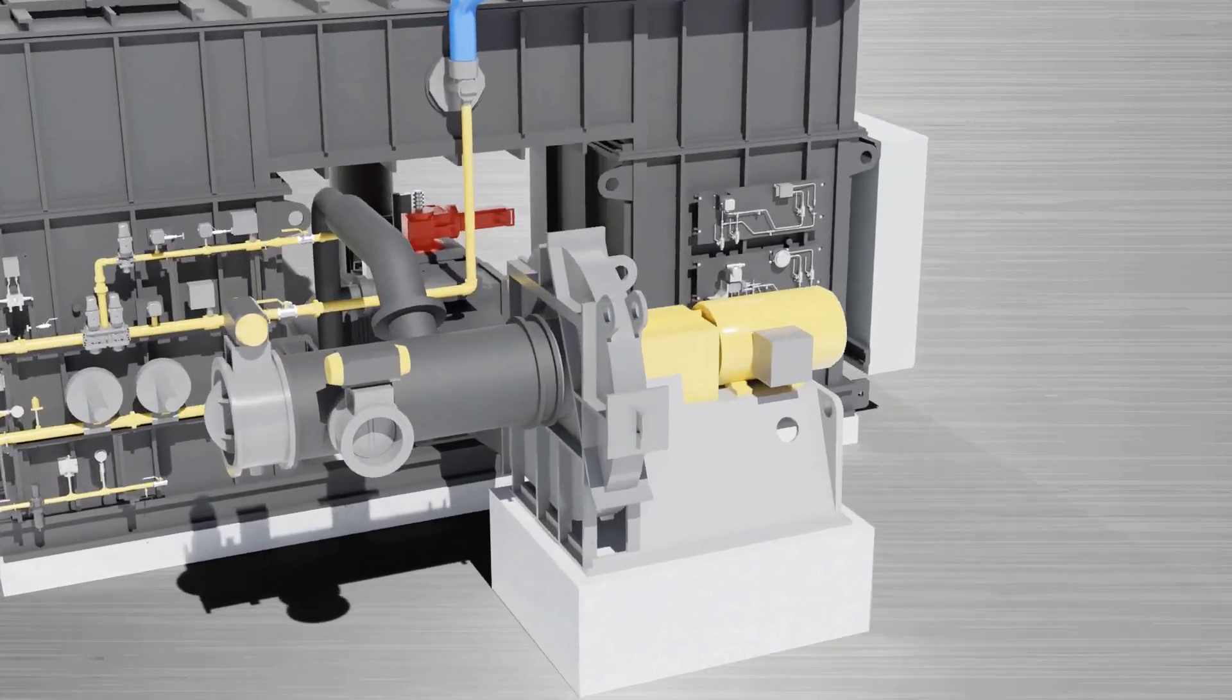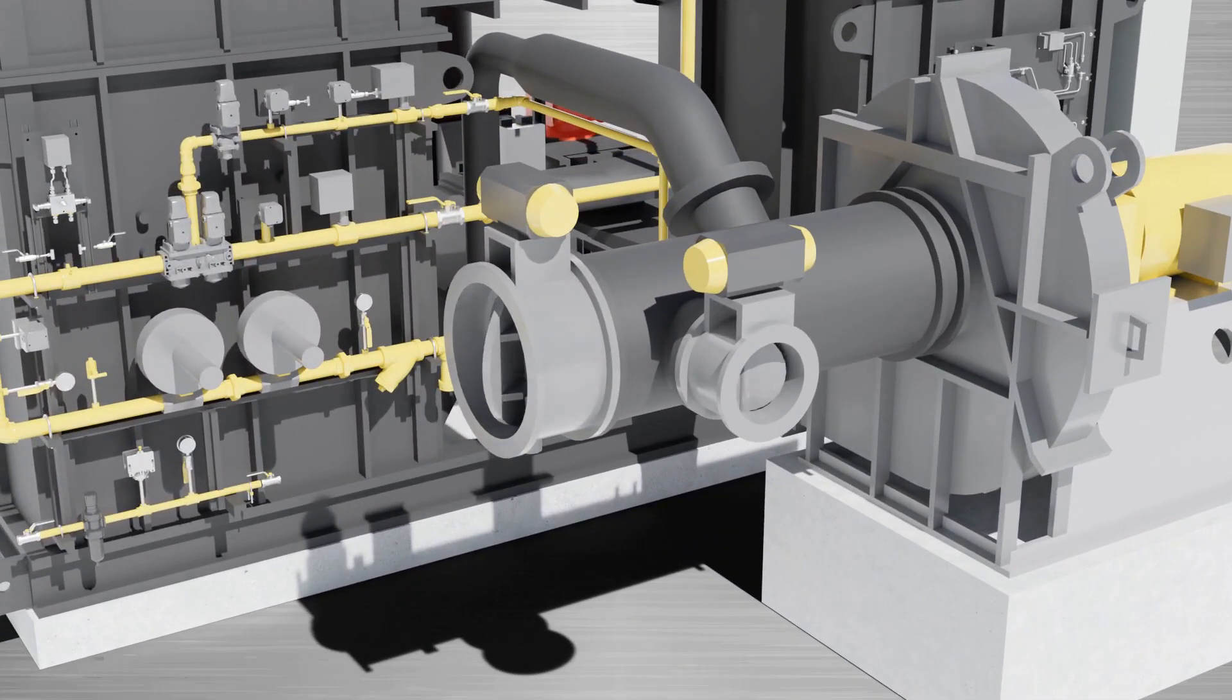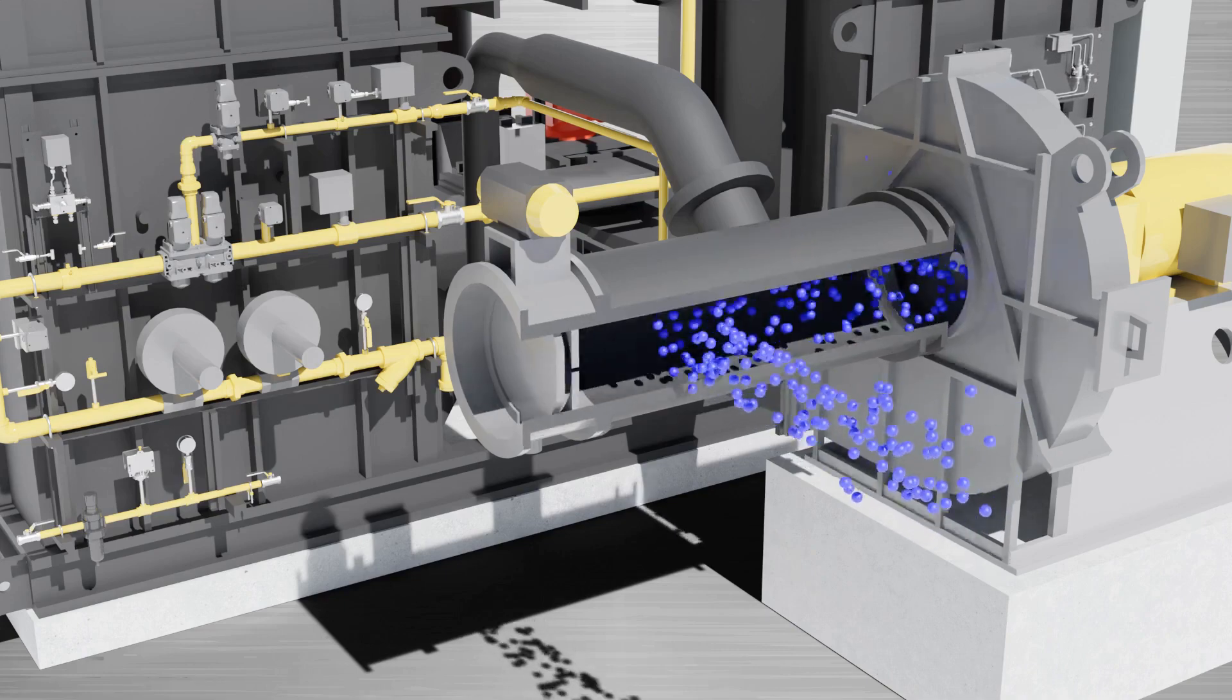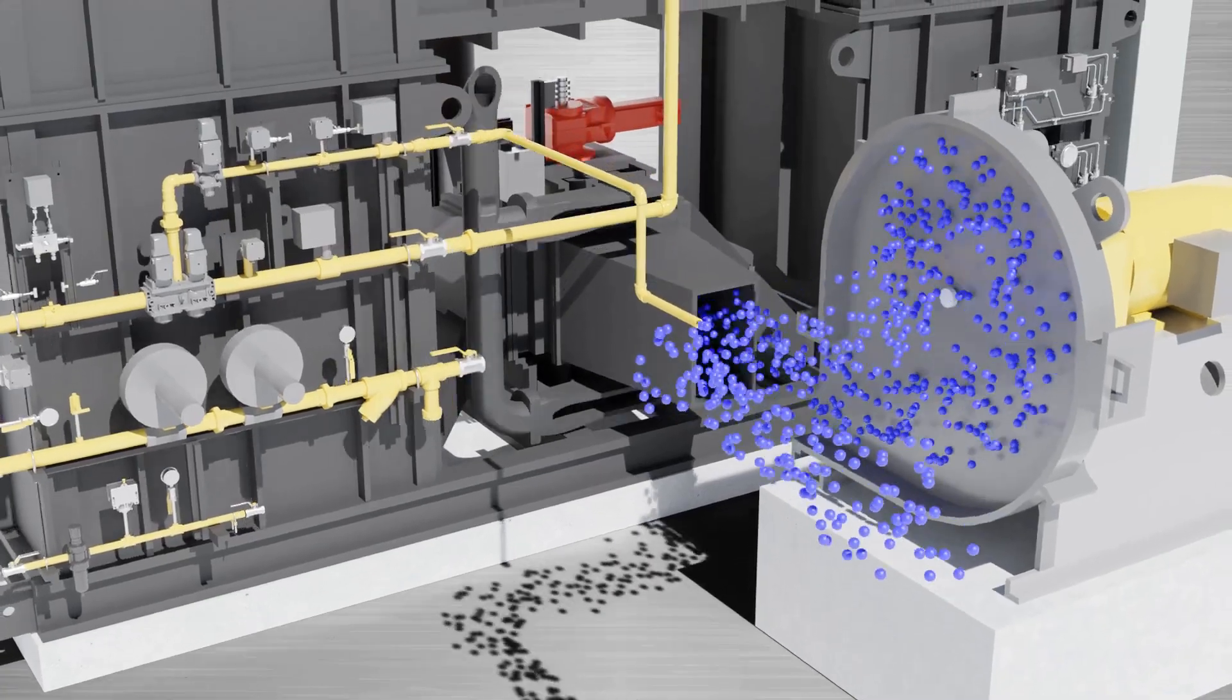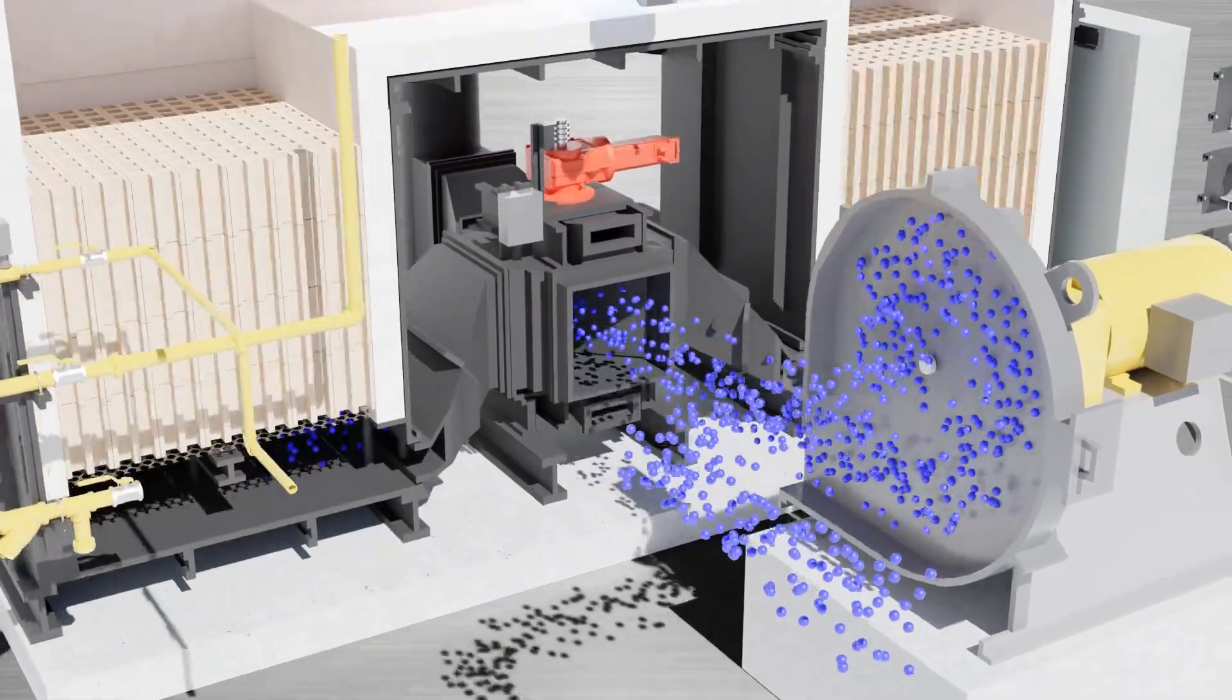Now let's take a look at the operation of the RTO. To begin preheating, the process damper is closed and the makeup air damper is opened. The process blower purges the vessel and begins to preheat the media using ambient air flow from the makeup air damper.